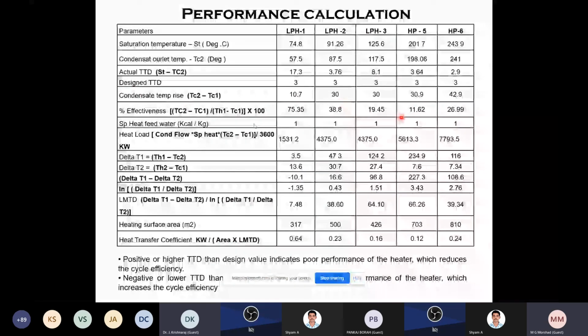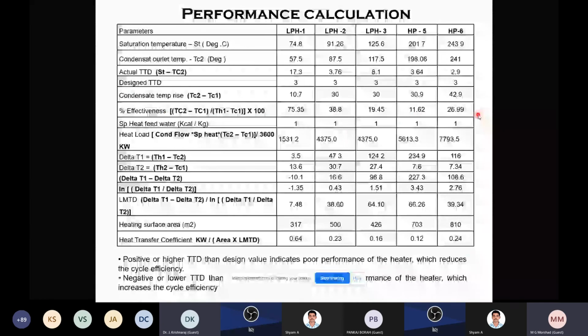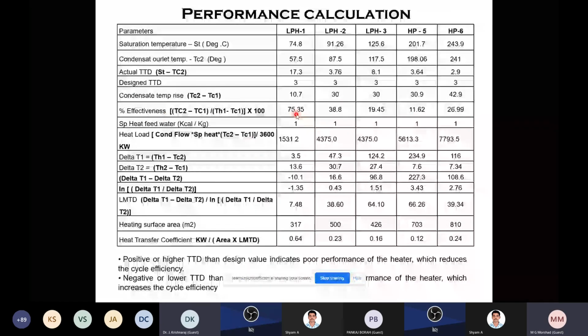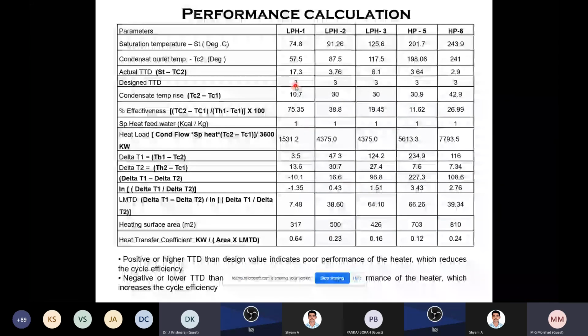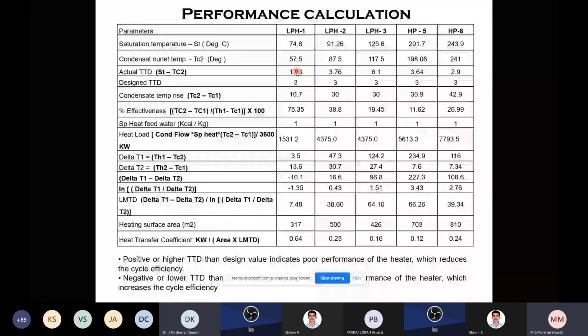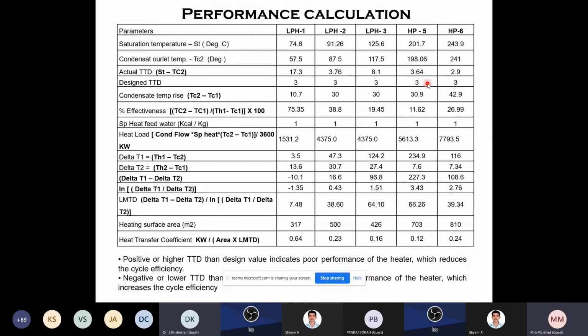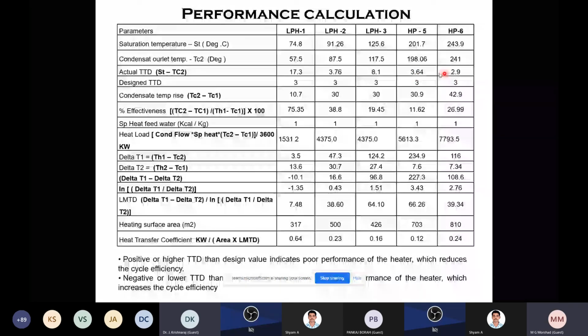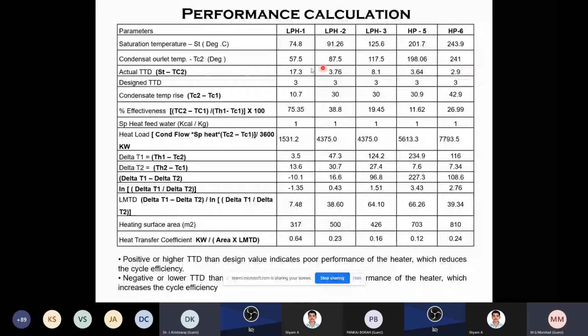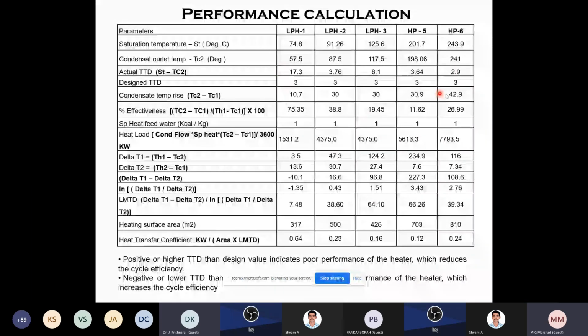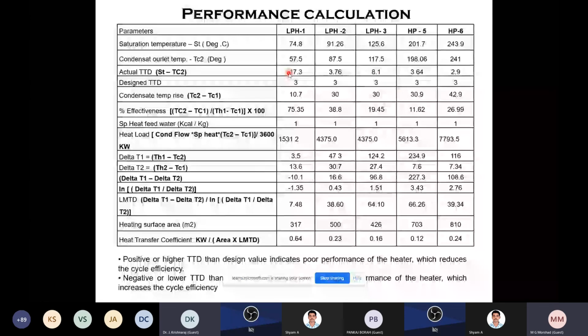We are calculating the condensate temperature rise and the effectiveness. Here you see the actual TTD is 17, and the design is 3, so the performance is not good. Here the performance is more or less okay. Here it is not good. Here more or less okay. Here it is very good. So by seeing this data, you can justify and understand which heater is working properly and which heater's performance is good or bad.